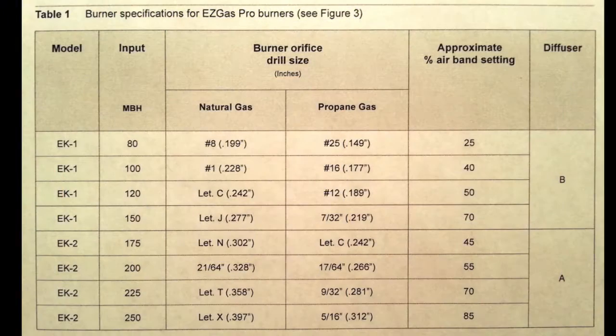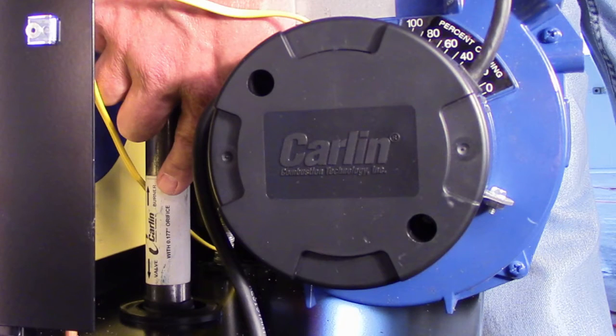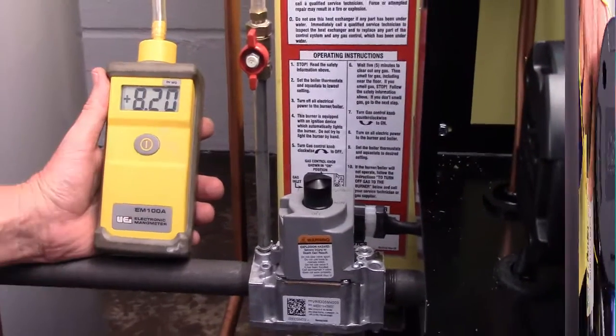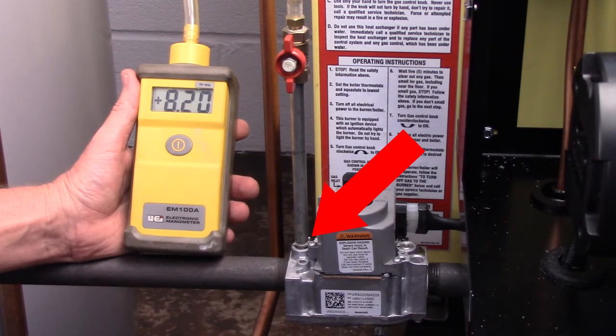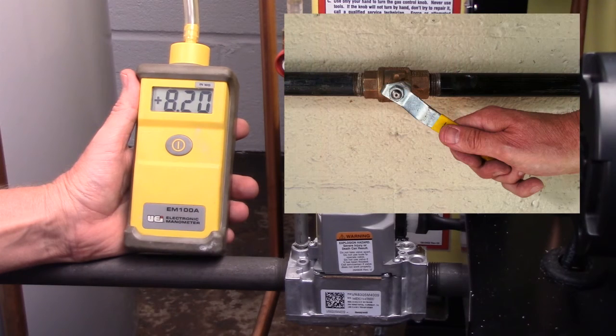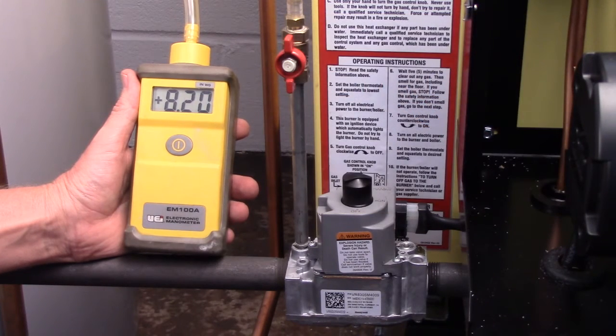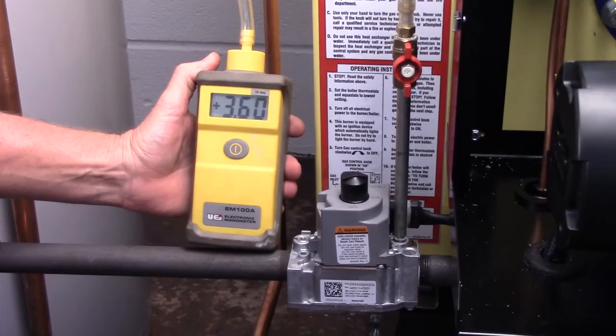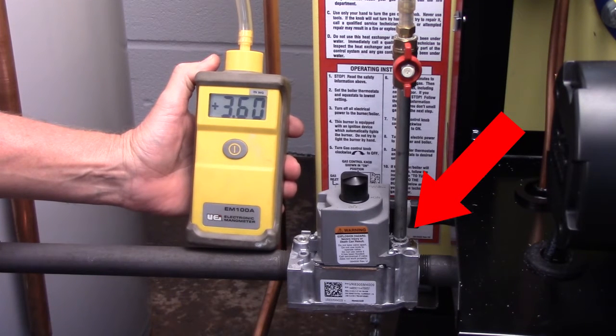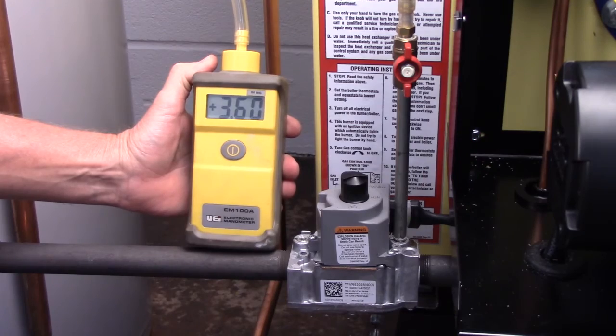The final settings will be determined by performing a combustion test with the airbox cover installed. Also check the orifice size against the gas burner settings table found in the EZ Gas Burner Manual Supplement for Energy Kinetics. Install a manometer on the inlet side of the combination gas valve to check supply pressure. If there is no pressure, trace the gas line to find out why there is no gas available. Check the main manual gas shutoff valve as it may be closed. The minimum inlet gas pressure is 5 inches water column with the burner firing and all other gas appliances operating. Next, check the combination gas valve outlet pressure. The manifold pressure should be between 3.2 and 3.8 inches water column.